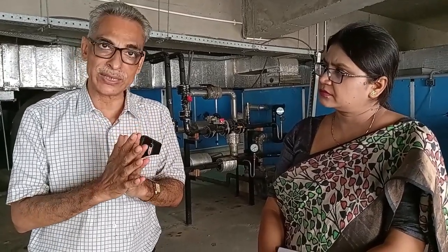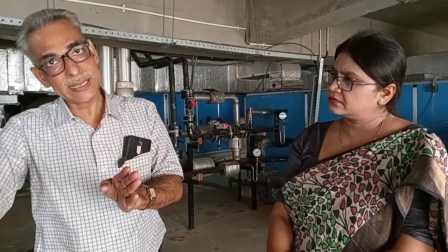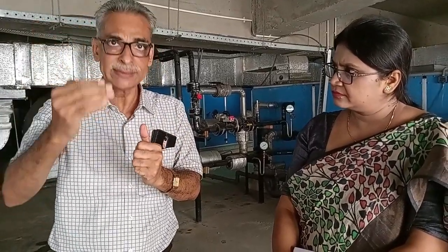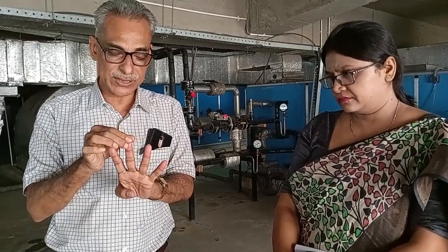Some of the dust particles will also condense, and then the air will flow to the second grid where hot water is coming out, on the other side. By this way, with cold and then hot, the excess moisture of the air is sucked out. So the air is getting dry, and its temperature is also maintained as we require for the clean room. Normally, 4 parameters in the clean room are maintained all the time: its pressure, its temperature, its humidity and its cleanliness. These 4 parameters we always need to maintain. The temperature, the pressure and the moisture are controlled from this individual AHU.